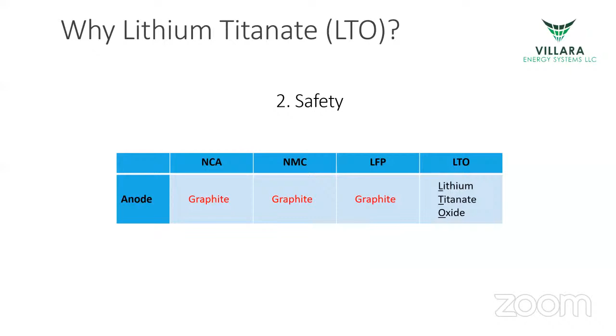Another reason is that lithium titanate is more tolerant of extreme temperatures. A lot of lithium-ion batteries claim operating temperatures down to -4°F and up to around 122°F. The dirty little secret of the battery industry is that most NMC and LFP batteries can't actually receive a charge below roughly freezing temperatures, unless they employ an active heating element — like an electric blanket for your battery — to preheat it so it can charge. That's because when graphite gets below freezing, you risk lithium plating if you try to charge the battery. So many won't charge below roughly freezing, though they can still discharge down to about -4°F. Contrast that with lithium titanate, which can go all the way down to -22°F and up to 131°F.